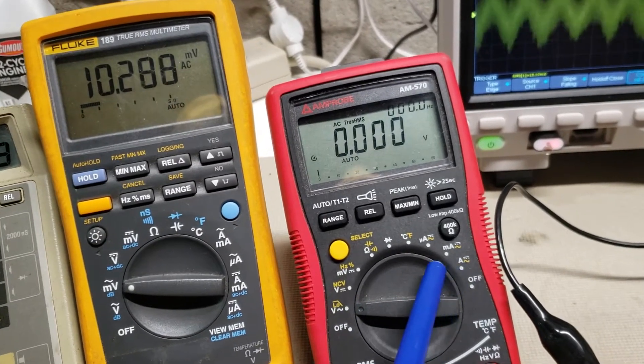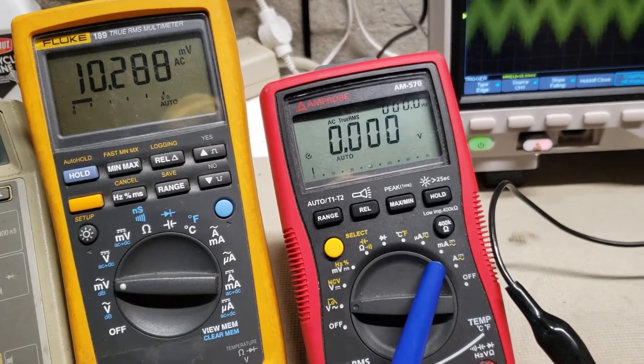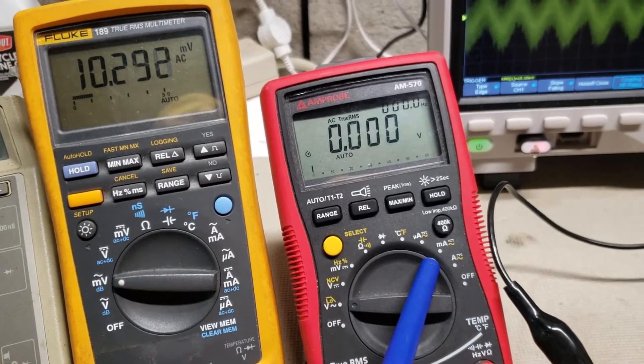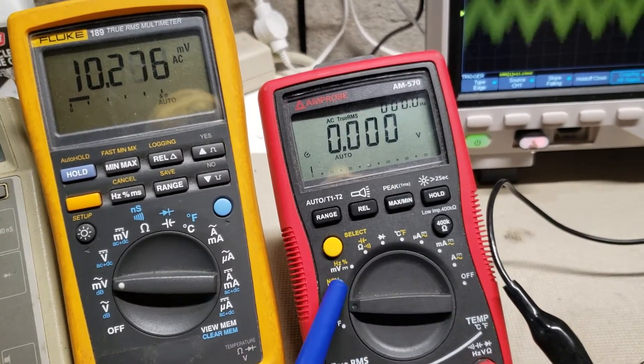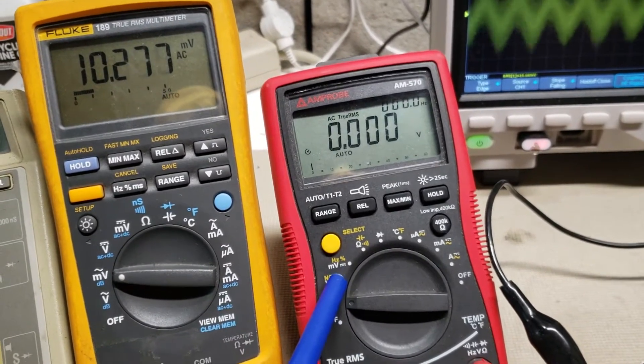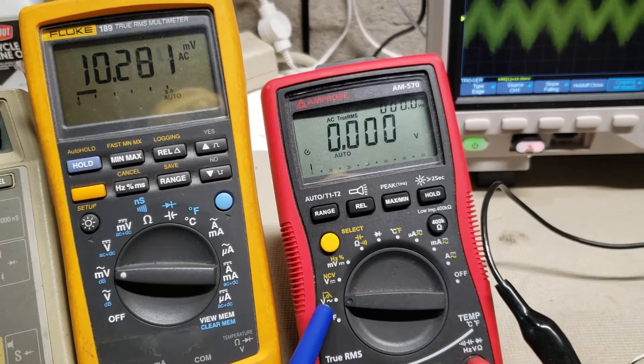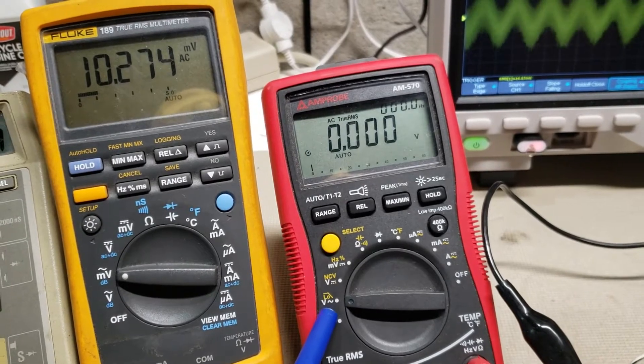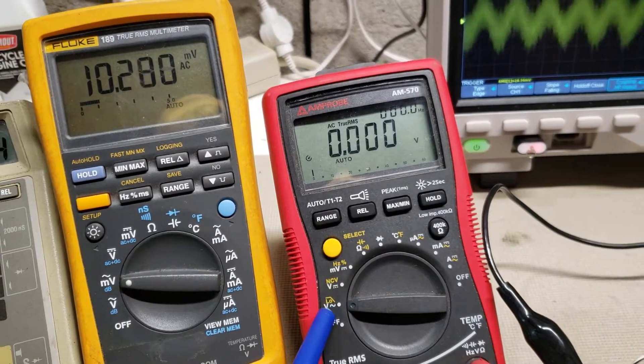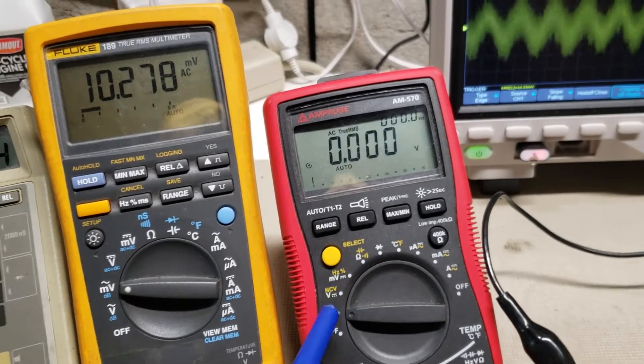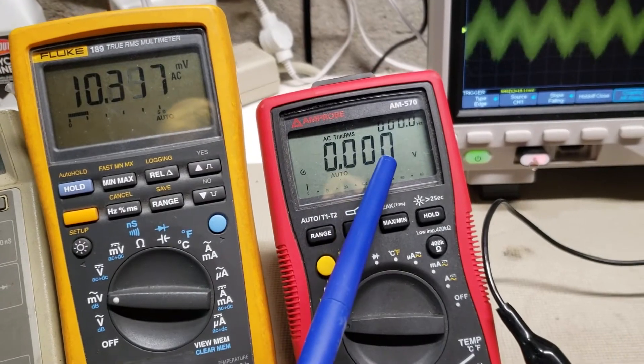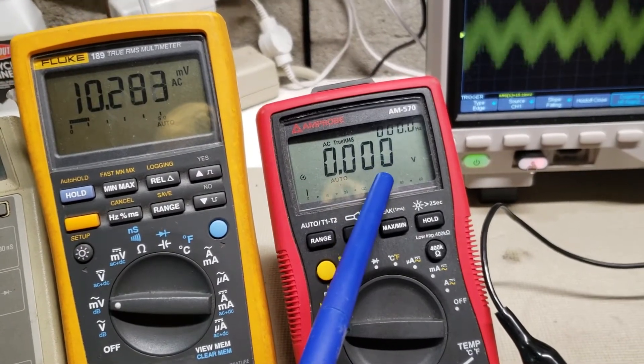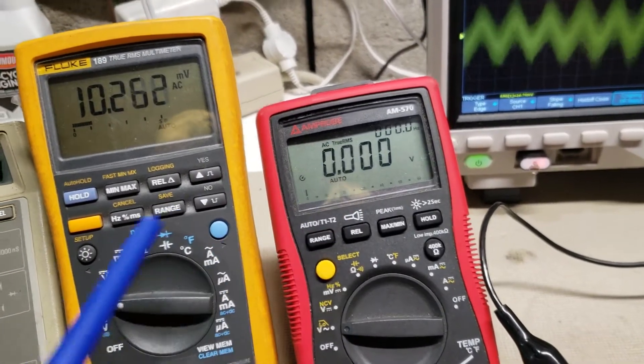But it goes to amps, it has milliamp DC and AC, and it has DC millivolt. But just AC volt with a low filter option. But the display says it can go down to one millivolt AC, true RMS.